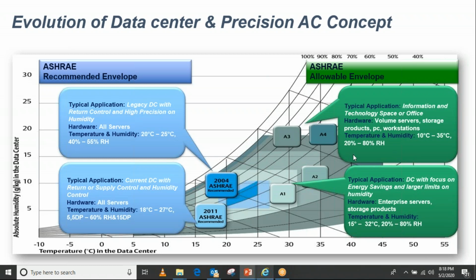And then you can see on the right side of the slide there are various different types of servers available, A1, A2, A3, A4 kind of category of servers, and these servers have different recommended and maximum limit envelopes, which are actually allowable envelopes. So the allowable envelope range is different than what ASHRAE recommends.